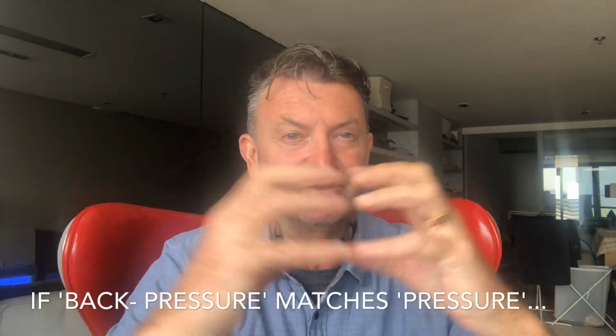So what is the back pressure? Well, the back pressure is created by reducing the number of jets or reducing the orifice of the jets, and then that will create a back pressure. And then we're creating back pressure by using tubing and hoses, right? It's called wall friction. So that's creating a back pressure. And then we've got back pressure coming from gravity, 5 psi per 10 feet or per floor of a building. Then all of this is back pressure, and that back pressure is coming against the pressure that you've got coming in, and if they equalize, then you've got zero flow.